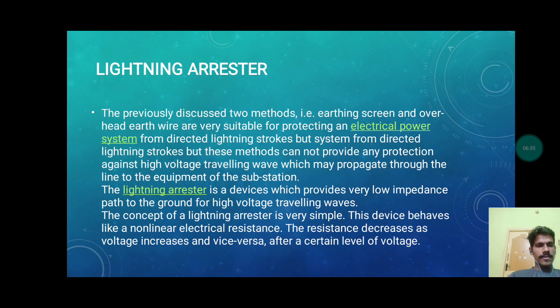Next one is lightning arresters. The two previously discussed methods, earth screening and overhead earth wire, are very suitable for protecting electrical power systems against direct lightning strokes, but these methods cannot provide any protection against high voltage traveling waves, which may travel through the line to the equipment of the substation. The lightning arrester is a device which provides a very low impedance path to the ground for high voltage traveling waves. The concept of the lightning arrester is very simple.